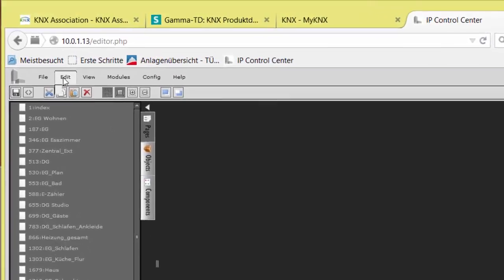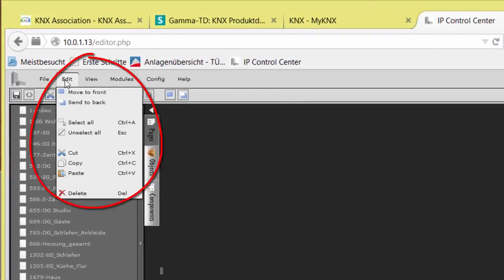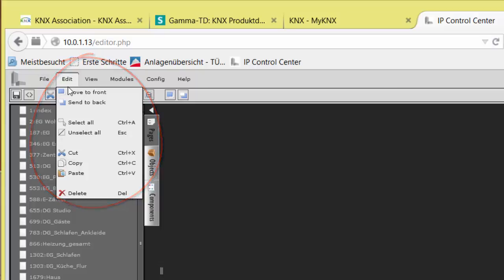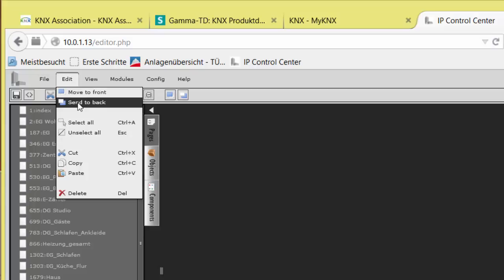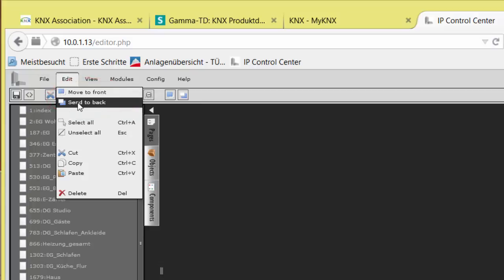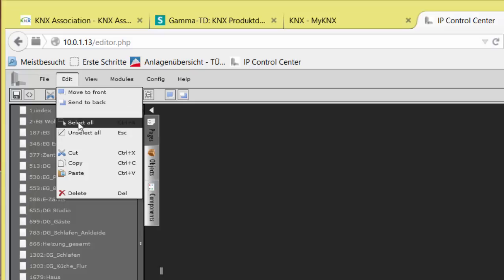Under the tab Edit, all tools can be found to move and align the display and operation elements. Move to Front and Send to Back repositions graphical elements relative to each other. That means if you have a separate status indication and a control button for the same function, then the button can be made transparent or invisible but placed directly on top of the status element to control it. In this case, the control button has to be moved to the front.